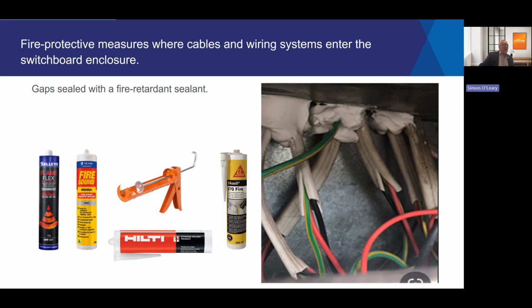The importance of having close-fitting holes is that a fire that starts in a switchboard can propagate outside the switchboard and typically chimney up through the top of the switchboard into a building or other structure, and allow that fire to propagate throughout a building. So it's quite important that we have these close-fitting holes around cable entries.